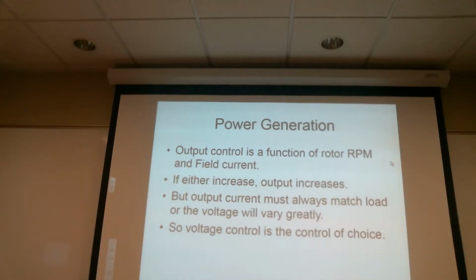Output control is always going to be a function of rotor RPM and field current. In the world of Continental, they typically connect the generator via a gear drive system, and when they switched from generators to alternators, they had to change the gear ratio a little bit. In the world of Lycoming, they drive them by belts off the bulkhead, off the starter ring gear. So they had to create a different pulley arrangement for the ring gear, because an alternator needs to spin quite a bit faster, a good 20 or 30% faster than a generator to put out the same equivalent.